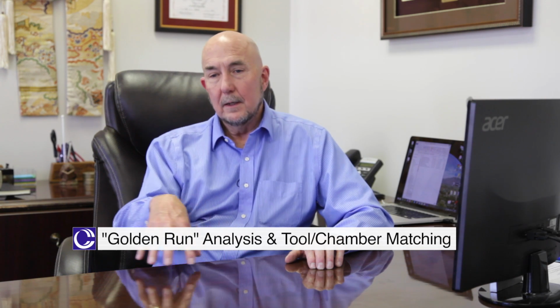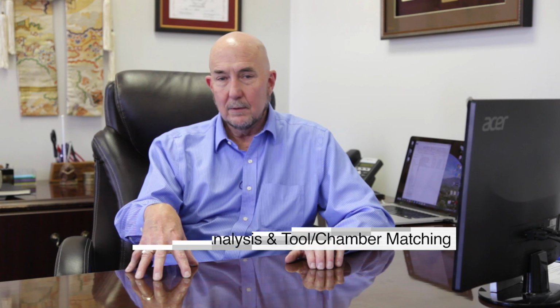Of course, another thing, once you understand the tool's behavior and have a good fault detection application, is that you then start to use it to compare tools across a fleet. With a set of similar equipment you want to have behaving in the same way, maybe you have one that behaves very well, but you're not quite sure why. So you do what's called a golden run analysis on that equipment, and you compare the key trace variables in one with like variables in similar equipment to see where the differences are and perhaps why those differences exist.